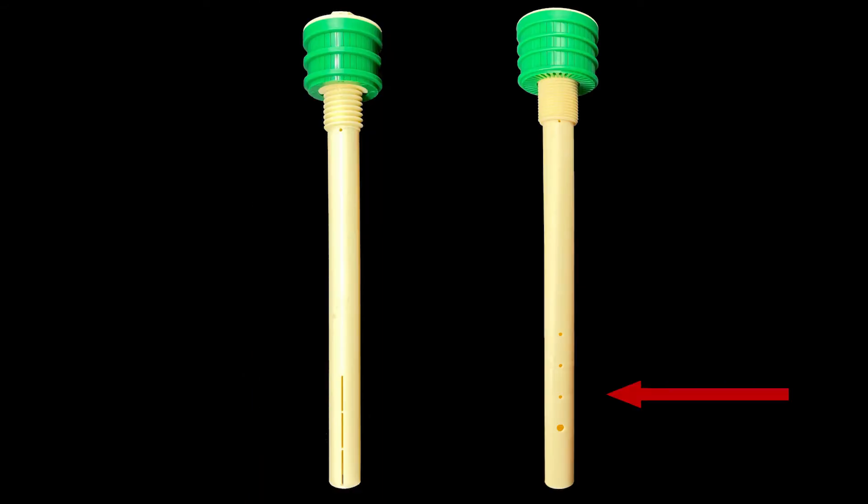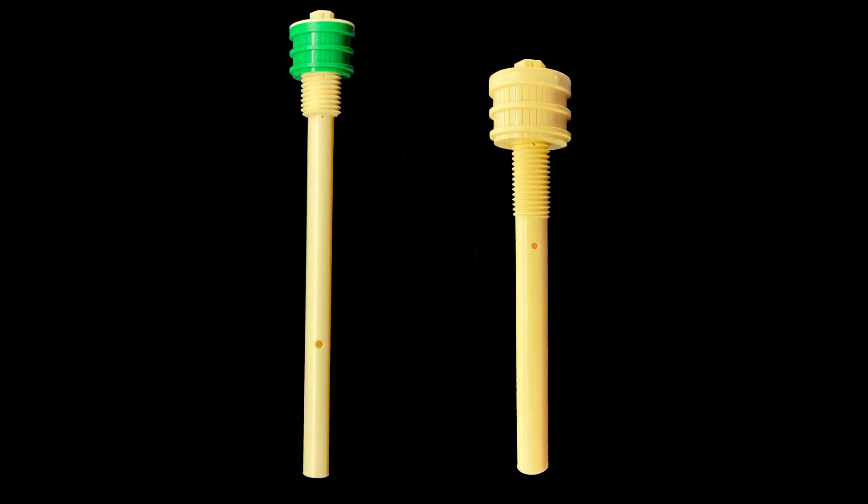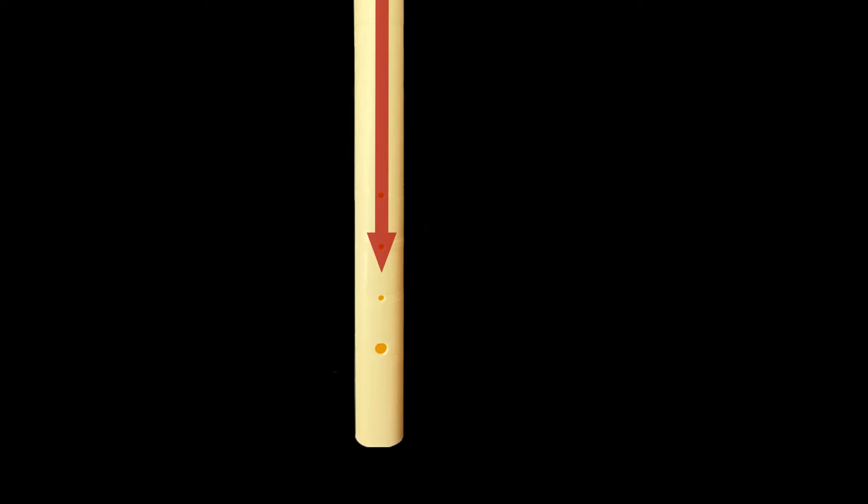Scour air enters the nozzle through metering holes or slots manufactured in the nozzle tailpipe. The size and location of these holes determine the depth of the air blanket at a specific airflow rate per nozzle.